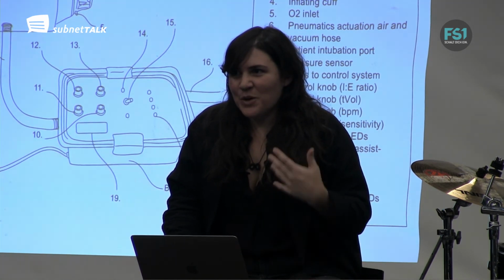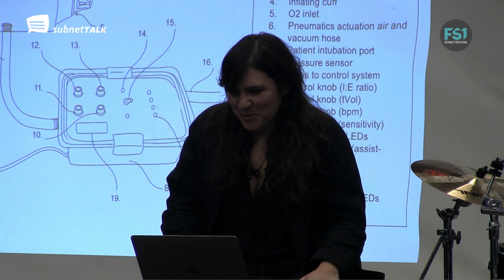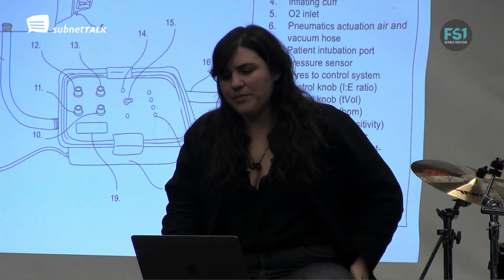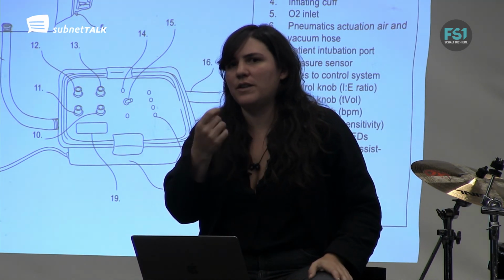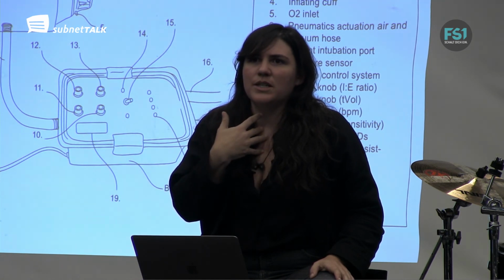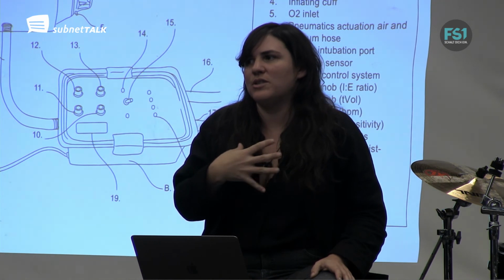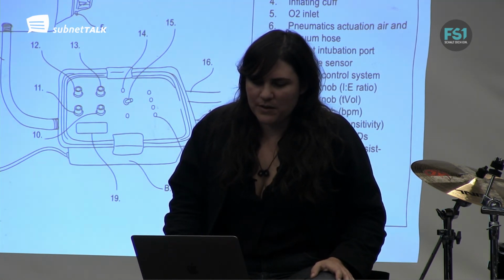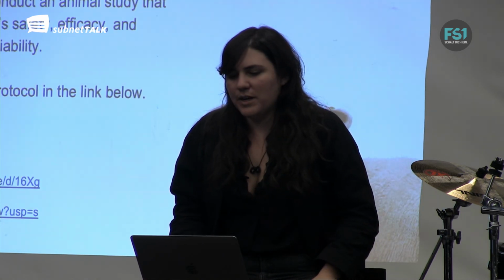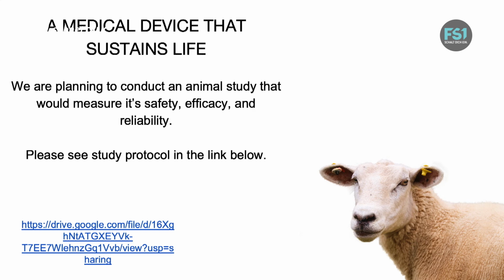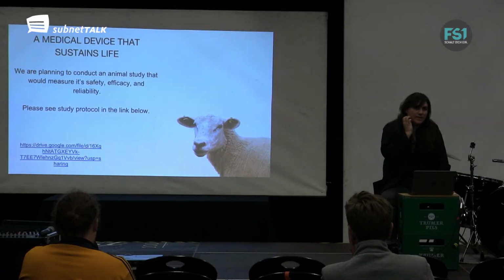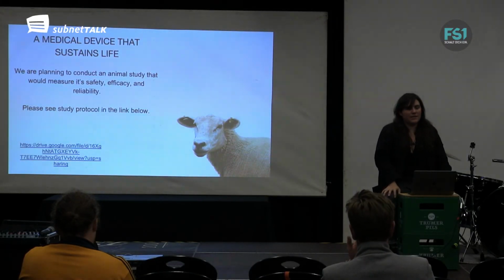So exhale deeply when you can, and remember. There are control knobs for tidal volume, for breaths per minute, and for the sensitivity of the inhalation that the patient is trying to make. We want to know how much the patient is able to breathe, so we can control the sensitivity for that. And lastly, we're currently on medical device animal studies. We're going to have 3 female sheep that we're going to test this device on. The prototype is fully functional at this point, and we will probably only test the automated mode rather than the assist control.